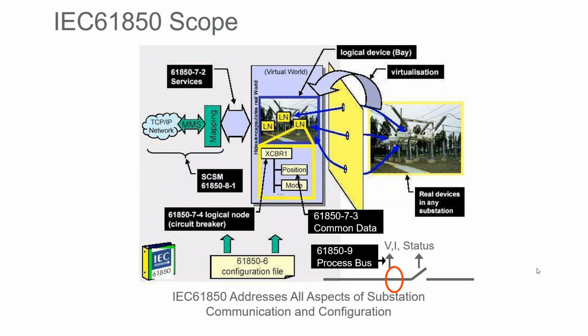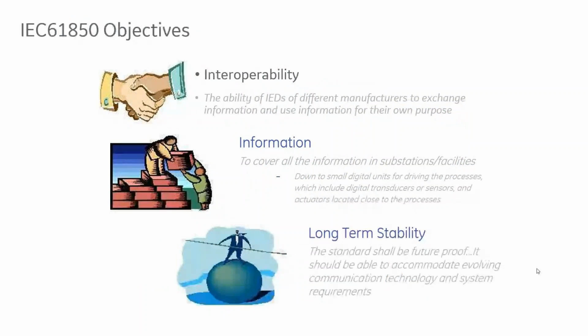I don't need to know what address that data is contained. All I need to know is that breaker number that I need to connect to. So the objective of 61850 is to be interoperable, to cover all information that we have in our facility, from the large generators to small meters, to have a long-term stability for being future-proof for any newer technology that we might want to take advantage of coming.